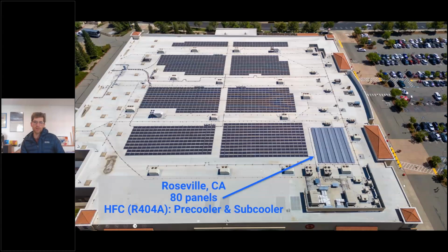So this is a site in Northern California. You can see our arrays in the bottom right over here. You can see there's solar panels on this roof as well. Essentially, the array for this site is sized to the cooling load of the refrigeration system. And so unlike solar, where you want to maximize the number of panels on a given roof, we just really want to put the right amount of our panels out just to meet the cooling load, and not more. Really, you get diminishing returns as you start to add more panels to the system.